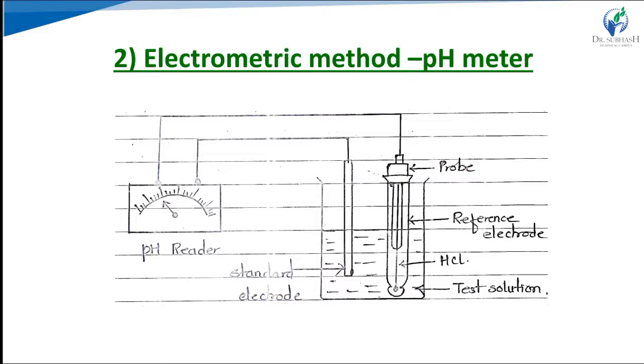So the pH meter essentially measures the electrochemical potential between a known liquid inside the glass electrode membrane and the unknown liquid outside. That is the difference. Since the operation of the electrode depends on the electrical resistivity of the glass, a change in temperature can also cause error.